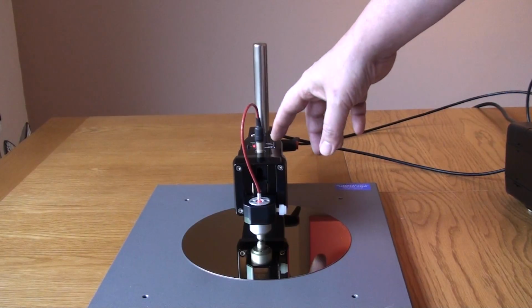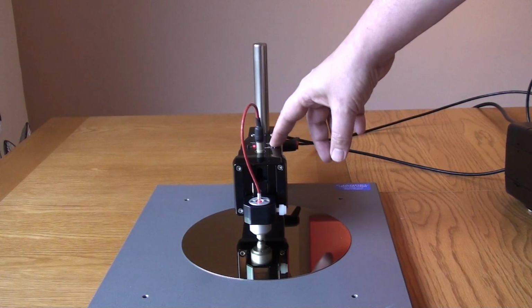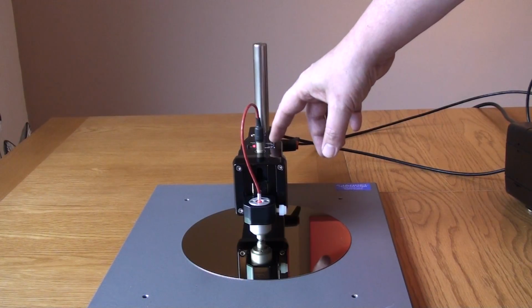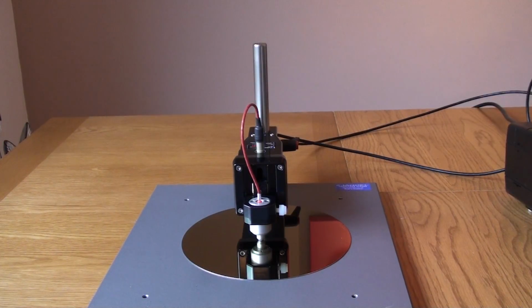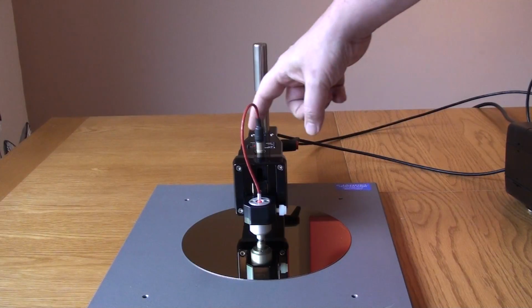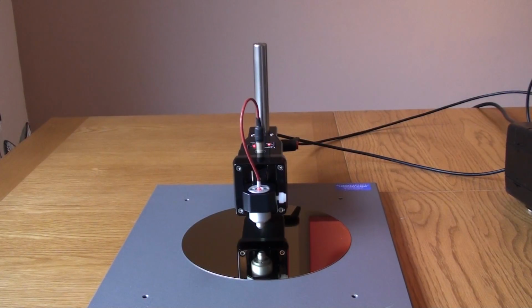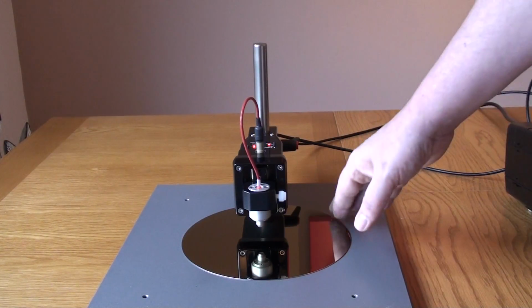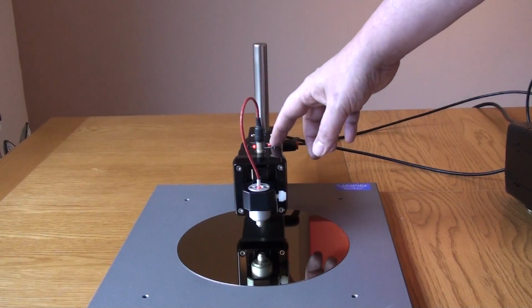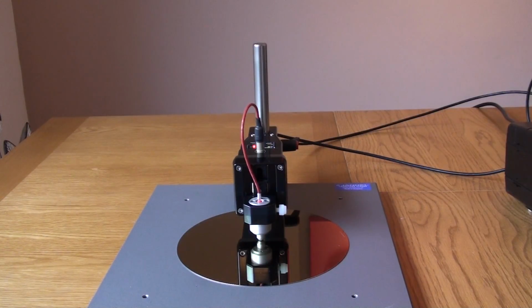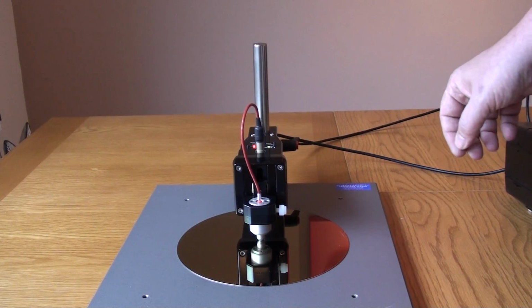To move the probe, press the sample button and lower the probe until the insulating pad touches the sample. At this point, the height is set and you press the needle load button. The probe moves back to the home position and is ready to be used. Pressing the sample button will lower the probe head onto the sample. Measurements can now be made.